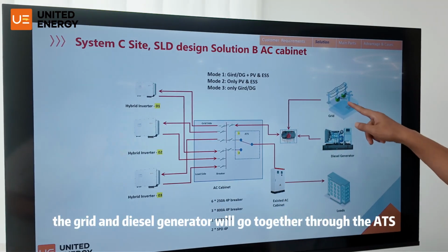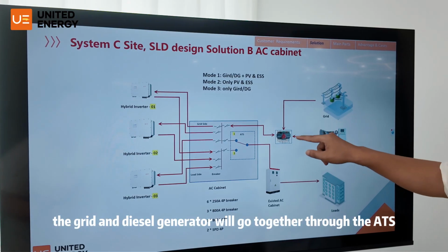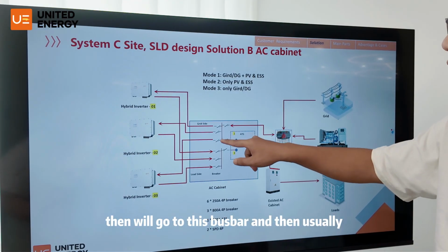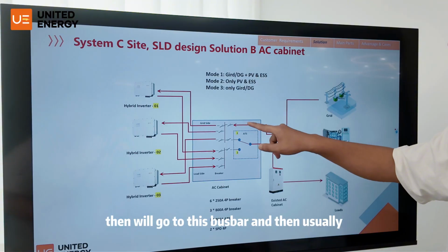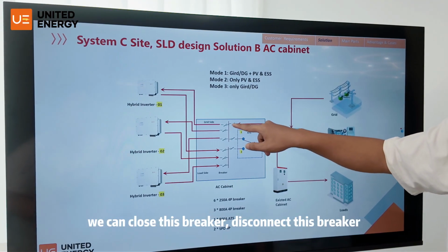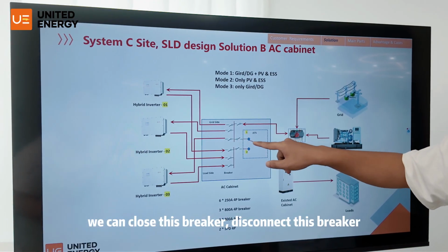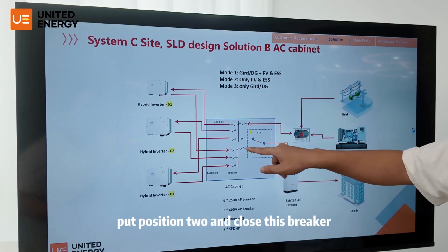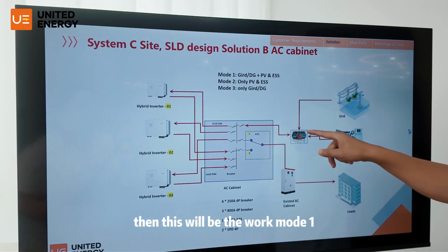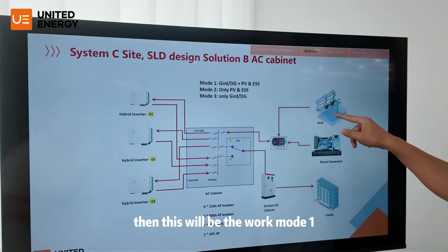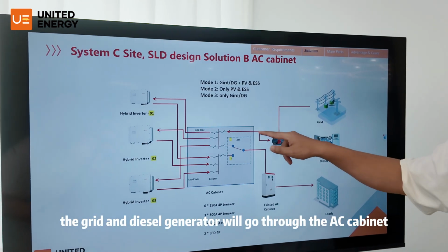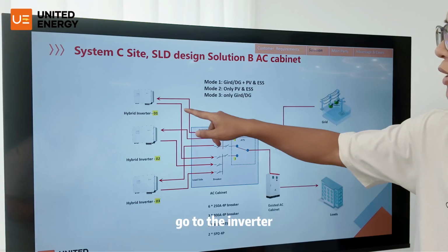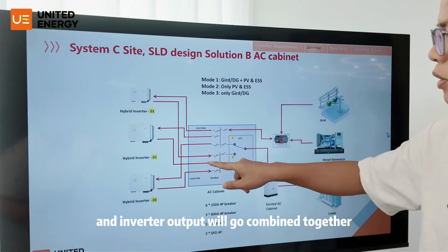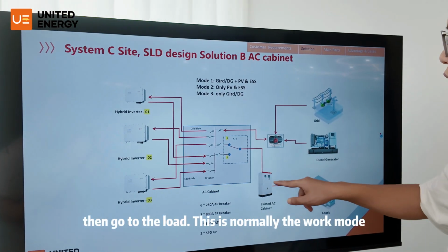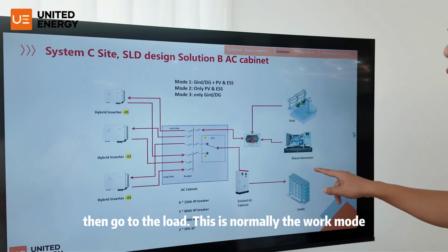You can see the grid and the diesel generator go together through the ATS, then go to this bus bar. And then usually we close this breaker, disconnect this breaker, put it in position 2 and close this breaker, close all of these breakers. Then this will be work mode number 1. The grid or diesel generator will go through the AC cabinet to the inverter, and the inverter output is combined together, then goes to the load. This is normally the work mode.